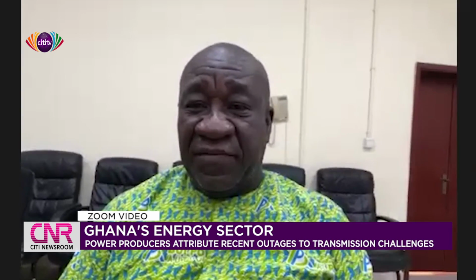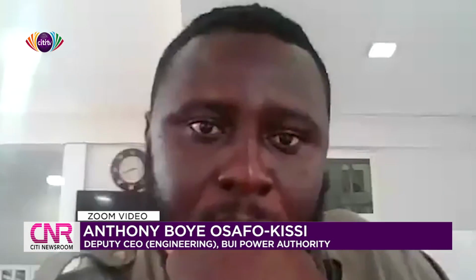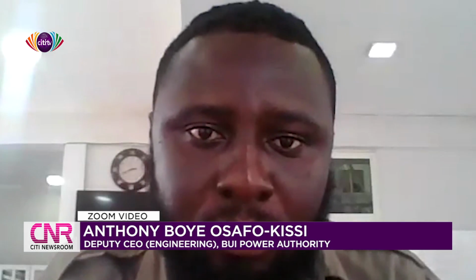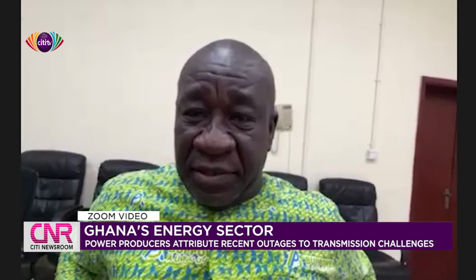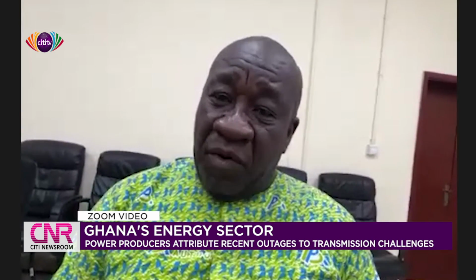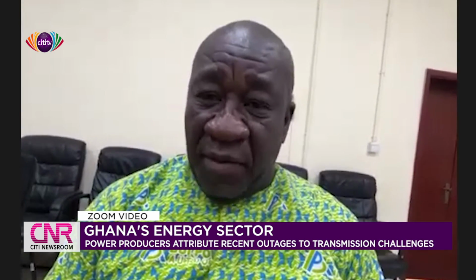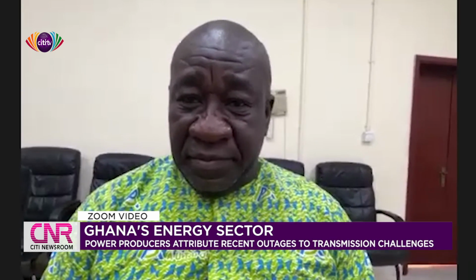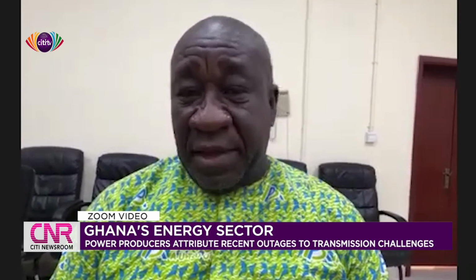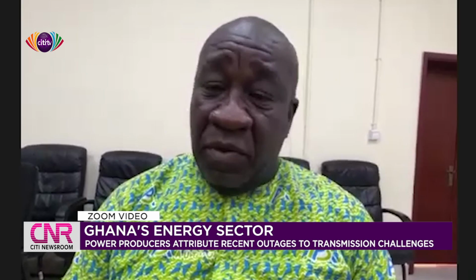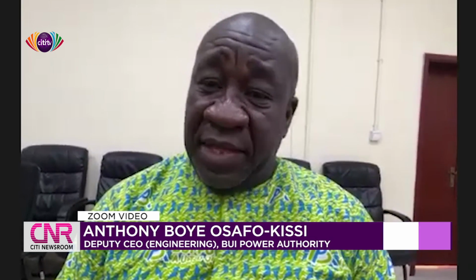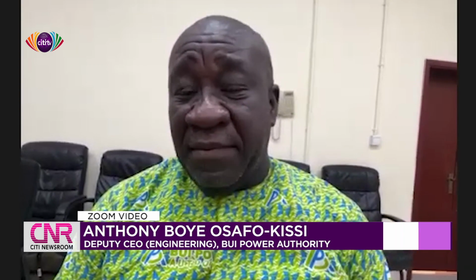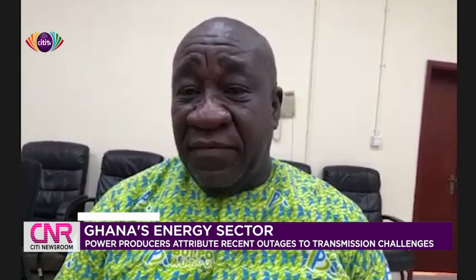Bui was at 400 megawatts, and in 2013, we added a 4 megawatt small hydro plant to it, so the total became 404 megawatts at Bui installed capacity. But currently, because of the low reservoir water level, we are just running one of our plants to produce reactive power in the daytime, and another one comes back at peak to serve load.